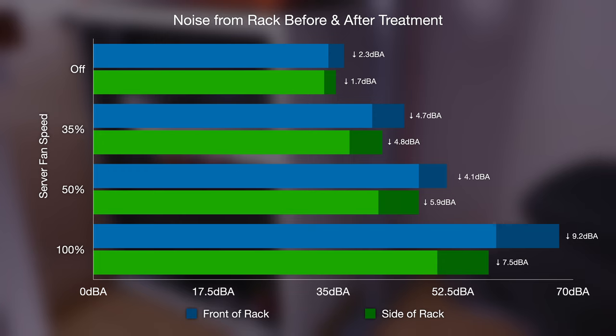But then when we introduce the server fan, even at 35%, we're seeing reductions well in excess of 4 decibels. And then with the server fan set to 100%, we're seeing reductions of 7 to 9 decibels. It's pretty significant. And this really impressed me. While these numbers don't seem particularly big, it's important to bear in mind that decibels are a logarithmic scale. So it's not like a linear scale, where going down by 4 decibels when you're really measuring levels in the 50s would be quite a small decrease. A 4 decibel decrease is quite significant.